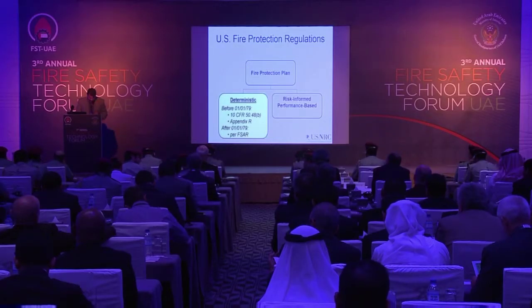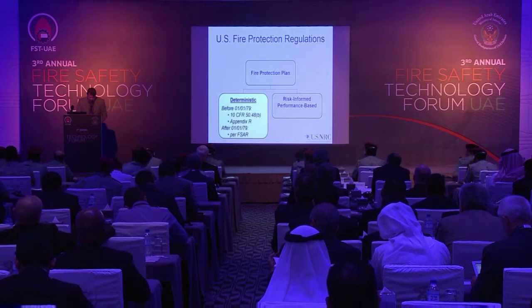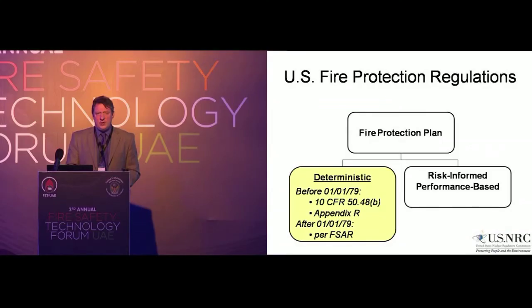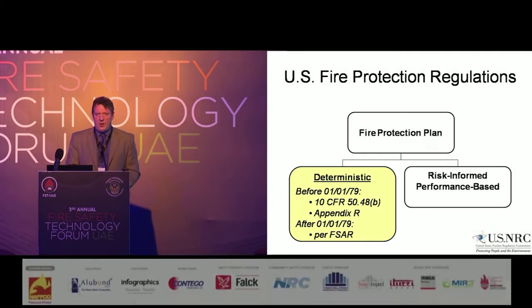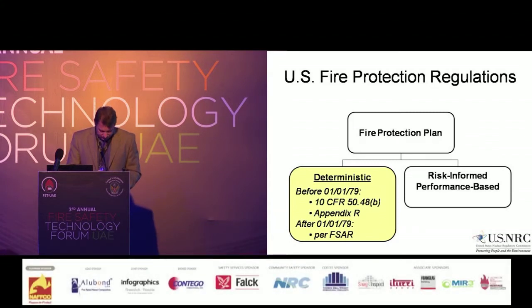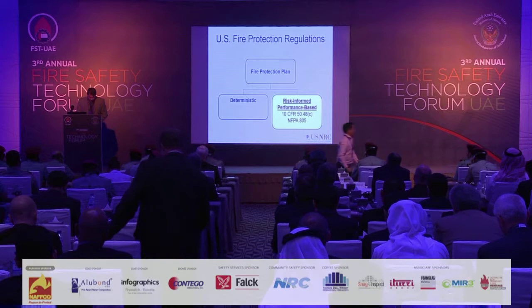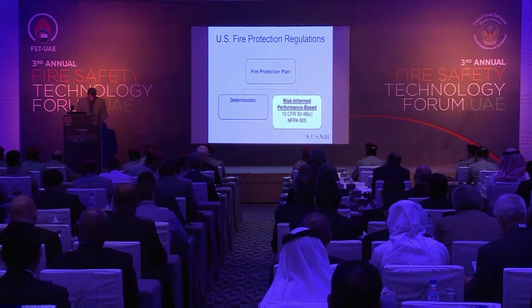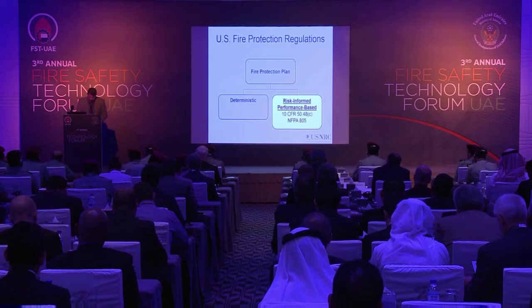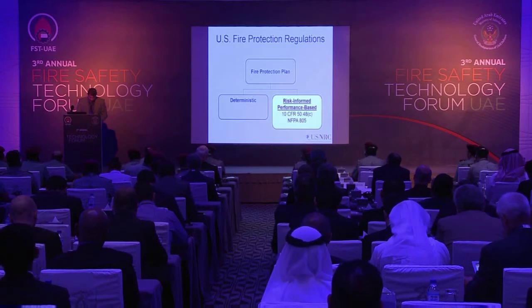Plants that were licensed after January 1st, 1979 were not subject to the 10 CFR 50.48(b) or Appendix R requirements, but also used a deterministic approach. And the approach was different in that the requirements became part of their licensing basis through license conditions. So in essence, they met the requirements in a different manner. In July of 2004, the NRC Commission added a new requirement which incorporates the National Fire Protection Association NFPA 805 by reference with a few exceptions.